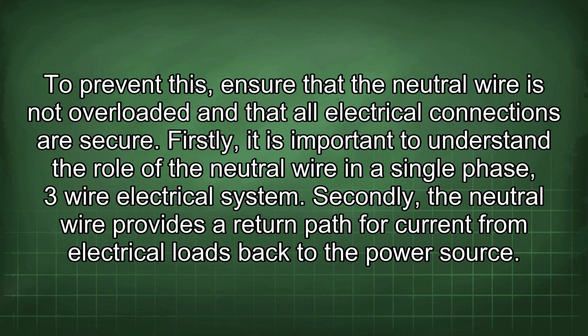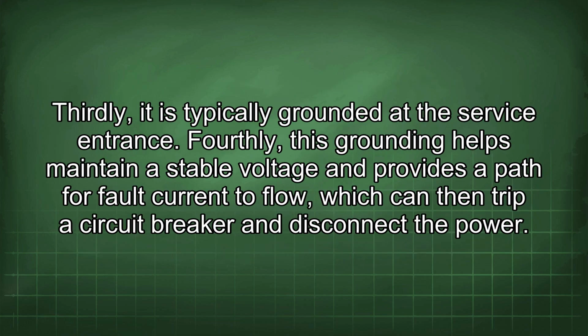Firstly, it is important to understand the role of the neutral wire in a single-phase, 3-wire electrical system. Secondly, the neutral wire provides a return path for current from electrical loads back to the power source. Thirdly, it is typically grounded at the service entrance. Fourthly, this grounding helps maintain a stable voltage and provides a path for fault current to flow, which can then trip a circuit breaker and disconnect the power.